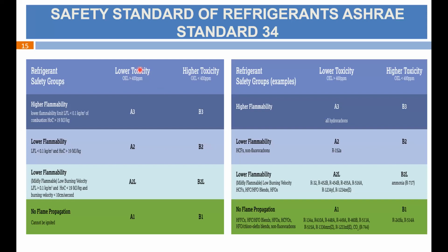If it is lower toxicity, the OEL value is higher, always greater than or equal to 400 parts per million. If it is higher toxicity, the OEL limit value is lower, less than 400 ppm. On the other side, there is flammability: refrigerants which are highly flammable, lower flammable, and another category which is mildly flammable. And lastly, there is no flame propagation, which is a very ideal situation.